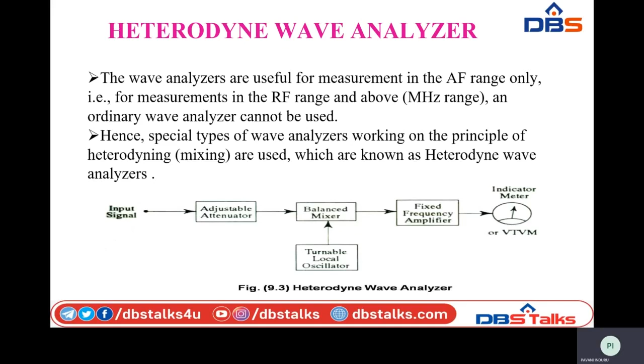So it is passed to the filter section where the required frequency is selected, and then that particular frequency component's amplitude is going to be amplified, and then the output is given to the vacuum tube voltmeter, which is calibrated in the decibel range to read its amplitude. Now, just a modified or detailed circuit of the heterodyne wave analyzer.